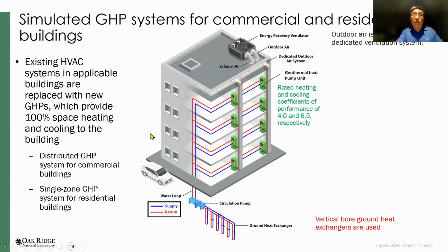For the commercial building, we simulated a distributed geothermal heat pump system. As you can see from this cartoon, the distributed system comprises many different water-to-air heat pump units at each room of the building, so they can provide heating and cooling independently for that particular room, with all the heat pumps connected through a common water loop.